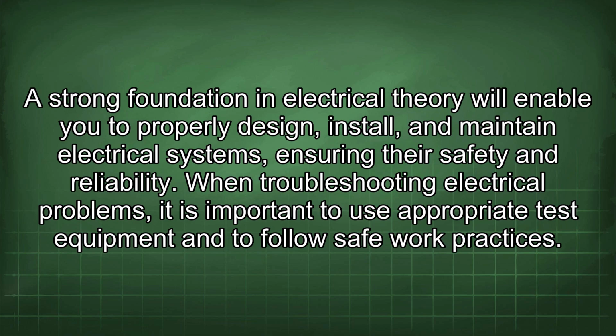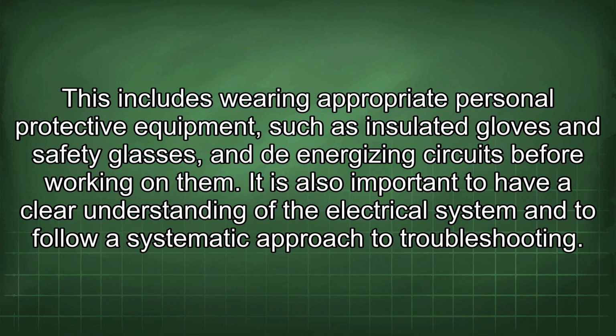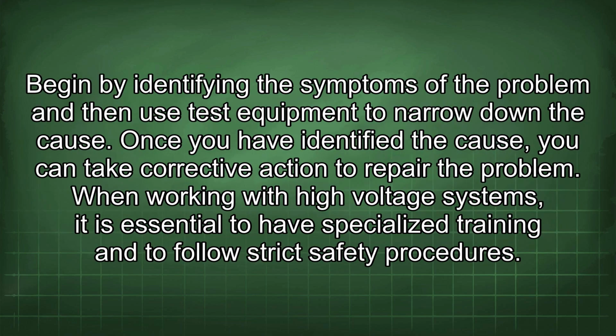When troubleshooting electrical problems, it is important to use appropriate test equipment and to follow safe work practices. This includes wearing appropriate personal protective equipment, such as insulated gloves and safety glasses, and de-energizing circuits before working on them. It is also important to have a clear understanding of the electrical system and to follow a systematic approach to troubleshooting. Begin by identifying the symptoms of the problem and then use test equipment to narrow down the cause. Once you have identified the cause, you can take corrective action to repair the problem.